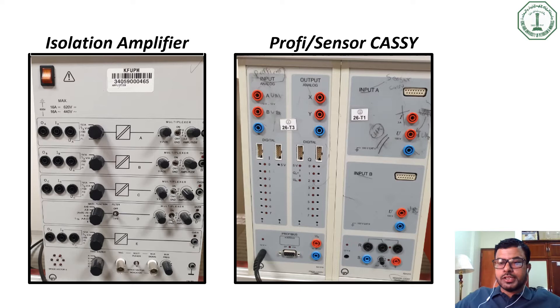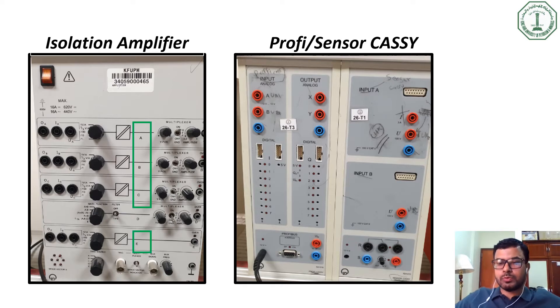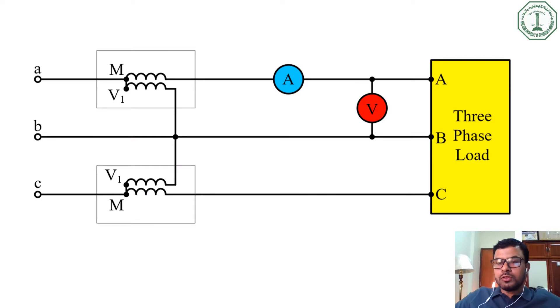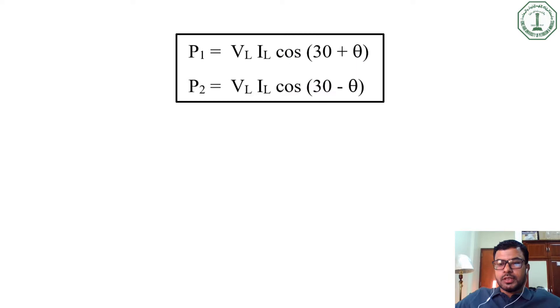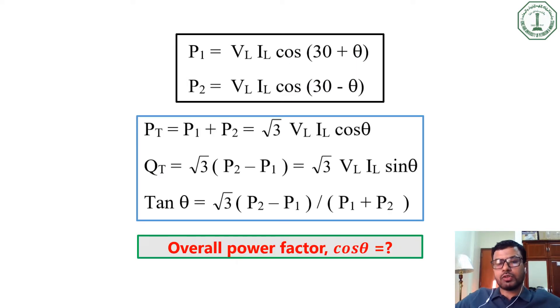Our available experimental setup has four measurement channels, meaning we can prepare a maximum of two wattmeters. However, in this experiment we have to measure three-phase powers. Therefore, we will be using the well-known two wattmeter method. These two wattmeters give us power P1 and P2, and using these formulas we can calculate the total real and reactive powers as well as the overall power factor.